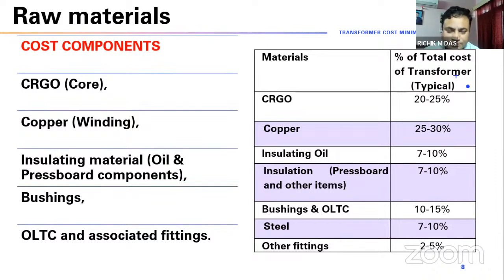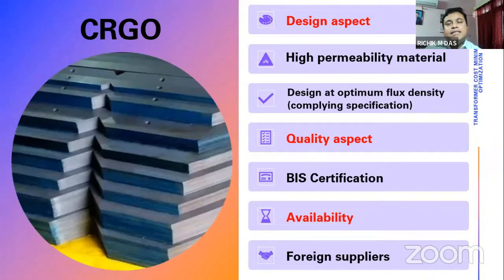How can we get the best CRGO? As far as design is concerned, now we have very good CRGO, because earlier the CRGO type was only M4, the conventional grade. Now most manufacturing plants source CRGO with high permeability grade, meaning HP grade, and all designers should design the transformer with optimum flux density, because CRGO with high permeability can withstand high flux density with low loss. That should also be taken care of by the designer.